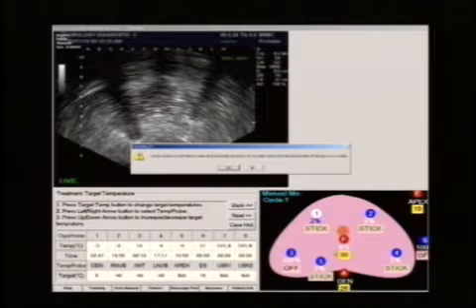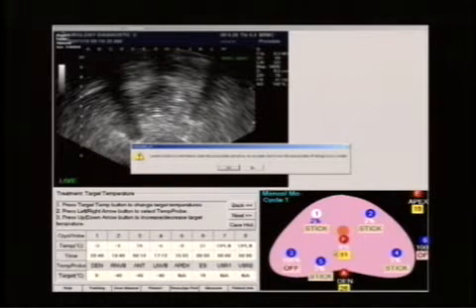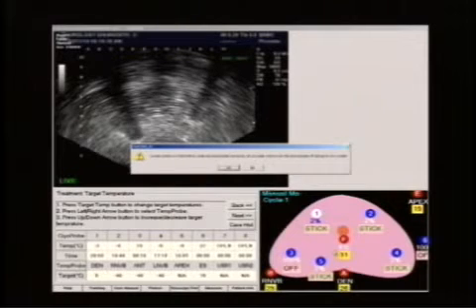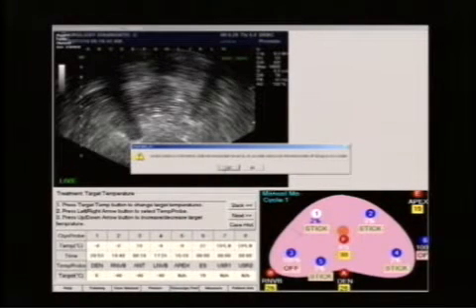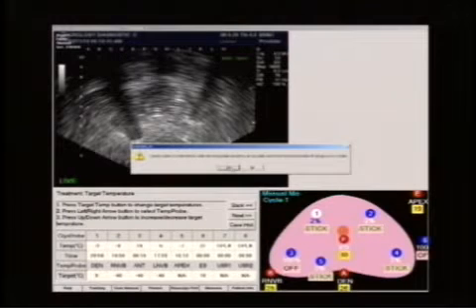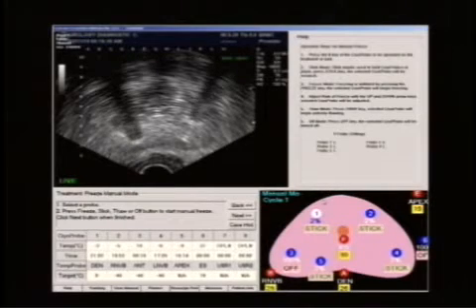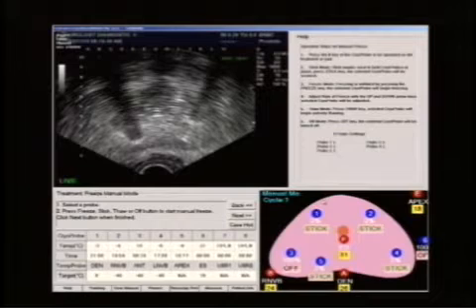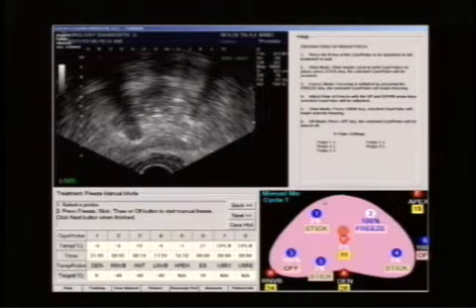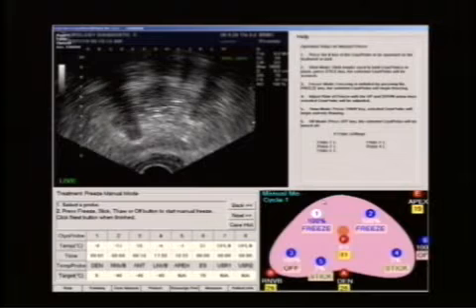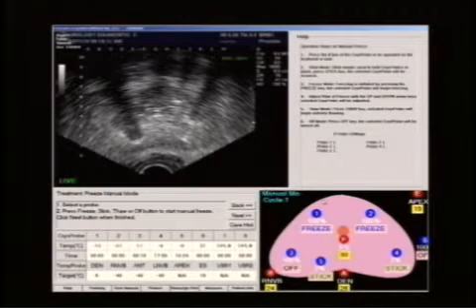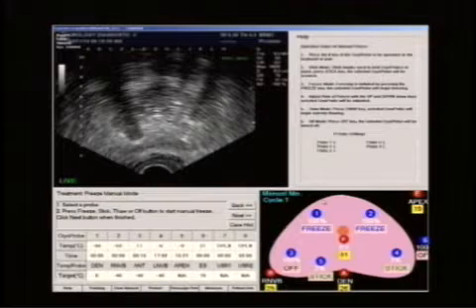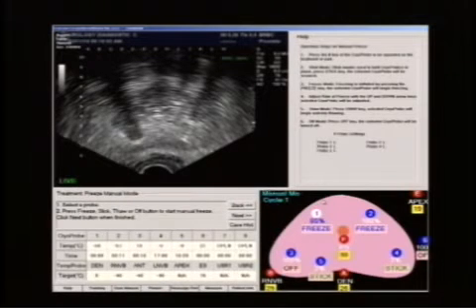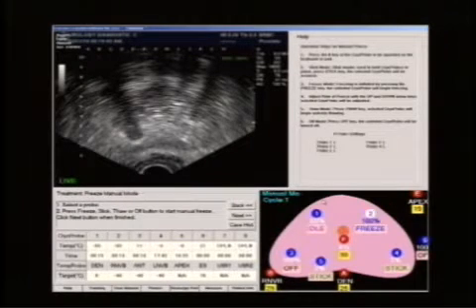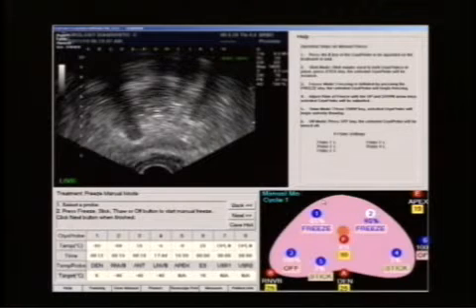The probes run on a freezing cycle of 10 seconds. If you have a probe on at 100%, the probe will be constantly running throughout the 10 seconds. We are actually going to have probes 1 and 2 on at 35%, meaning for 35% of that 10 seconds the probes will be freezing, and for the other 65% of that 10 seconds the probes will not be freezing. So again, this will give us a nice, gentle, controlled freeze anteriorly. So we're going to 35% anteriorly, right.